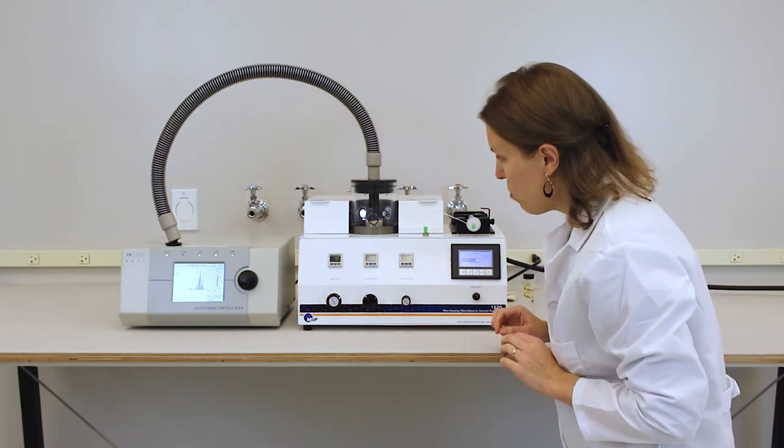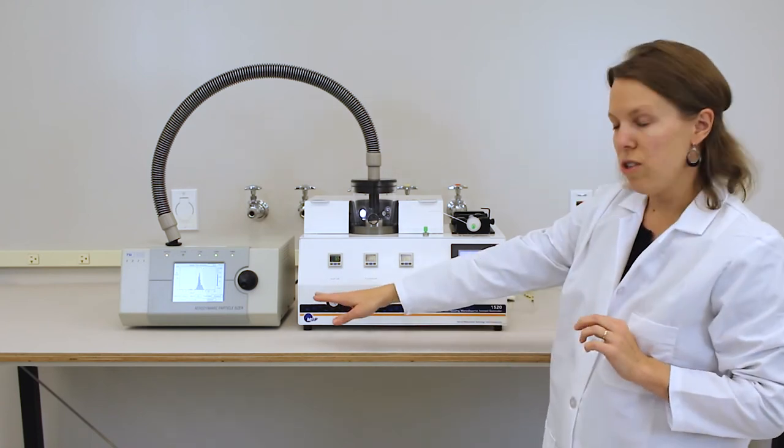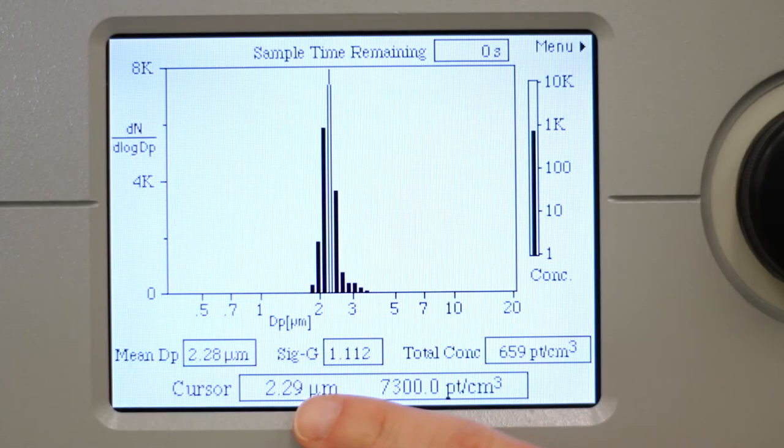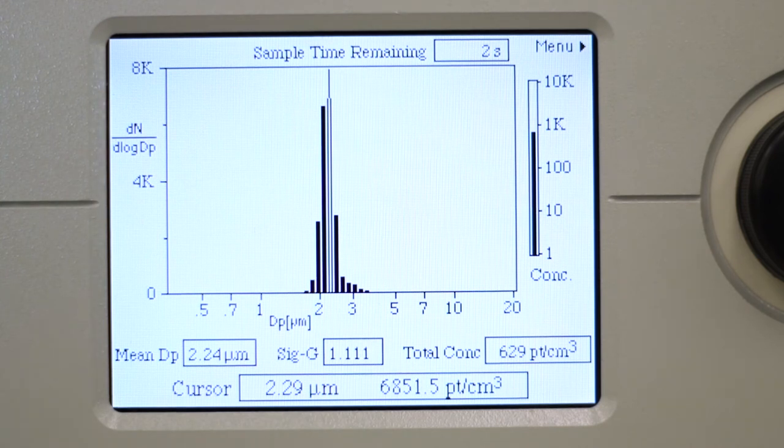Once the jet is stable, we can turn our attention to the aerodynamic particle sizer where we can start to see the generated particles being measured. Our target was 2.3 microns and we can see that the mode size is right around 2.3 microns.